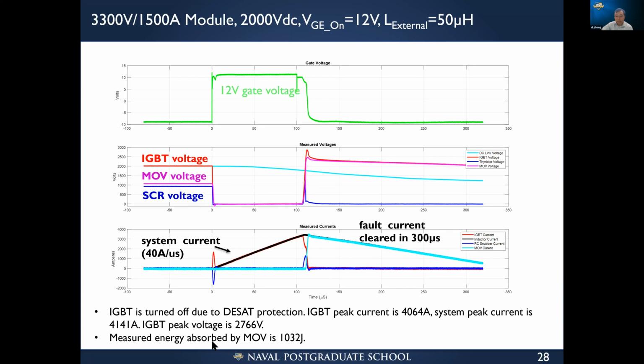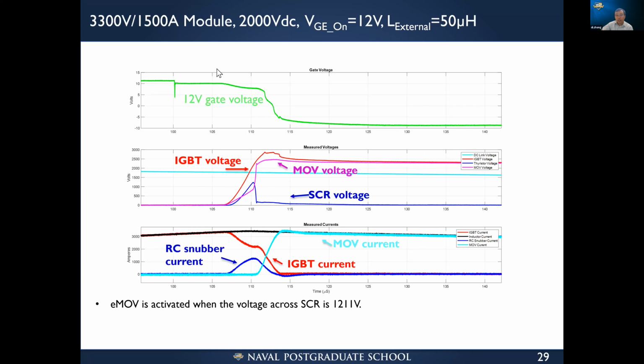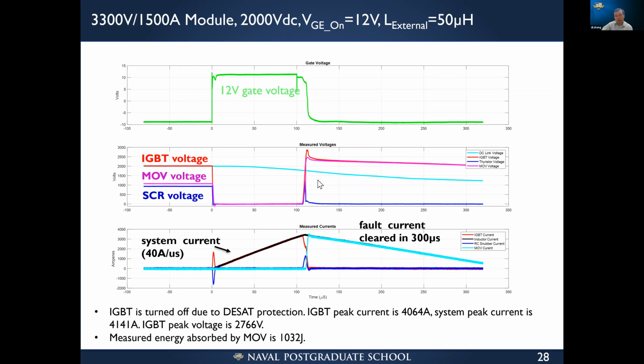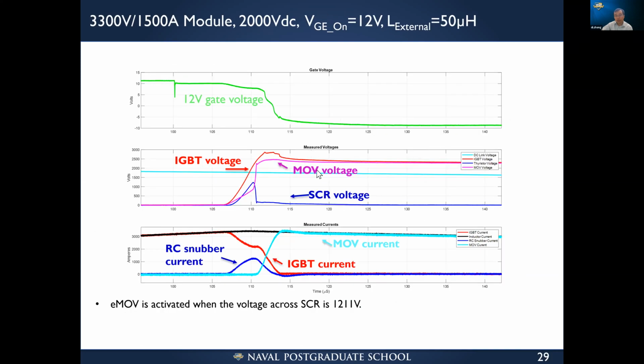Okay. The measured energy absorbed by the MOV is about 1 kilojoule. And again, this is already the worst case. We are using one single pole to clear the fault. Right? This is only a zoom-in of the waveforms of the previous test result. Oh, sorry, zoom in on the waveforms here, to show more details of what happened during switching.